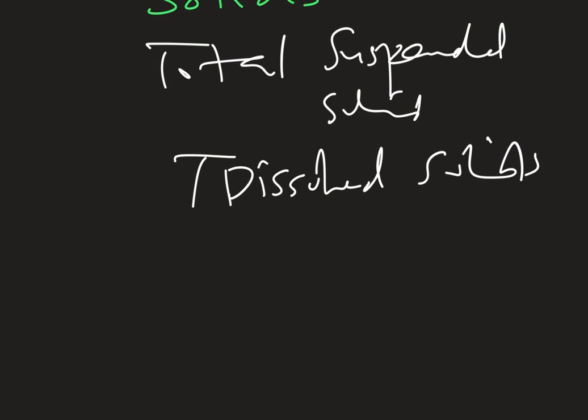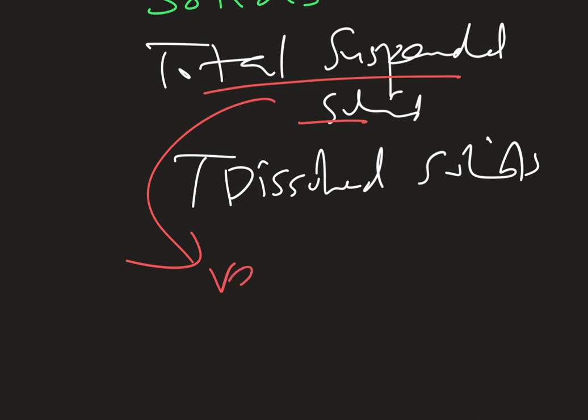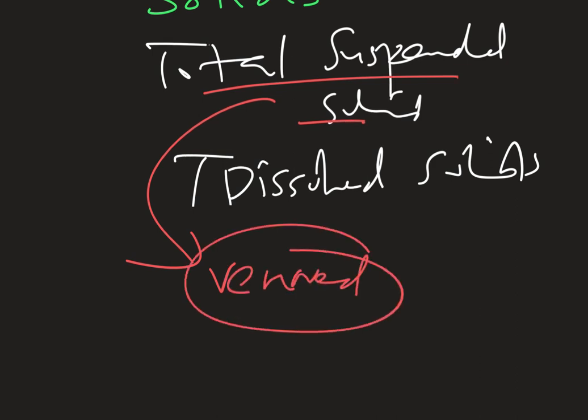For example, COD at 60,000, like palm oil wastewater, where you have oil and grease contained. The solids might be about 120,000 milligram per liter, with total suspended solids about 20,000, so you end up with a lot of total solids. That kind of scenario is what we have to cater for. So what is the significance of total suspended solids? They have to be removed in the plant.